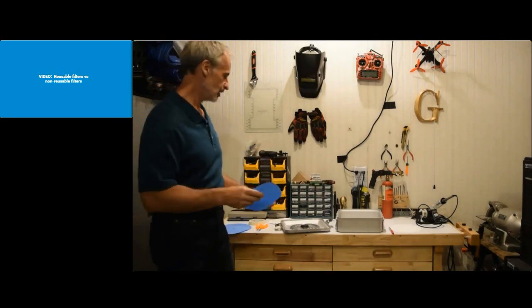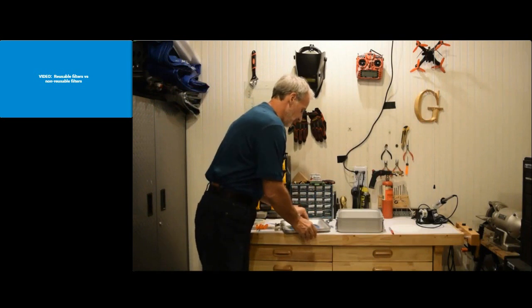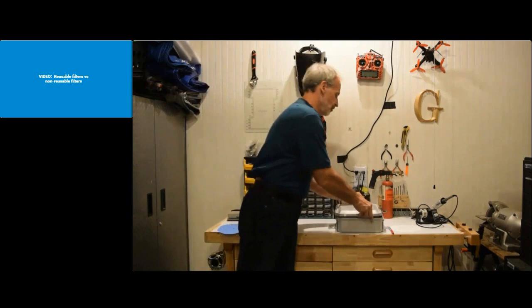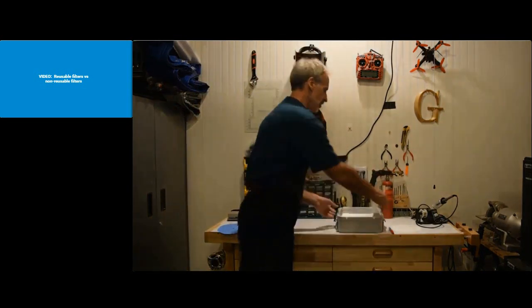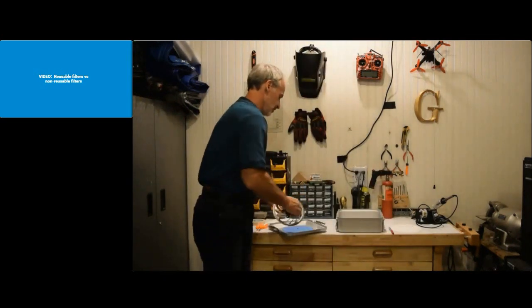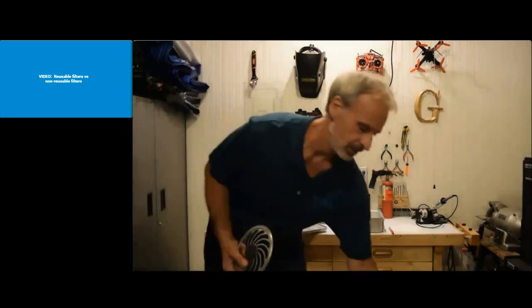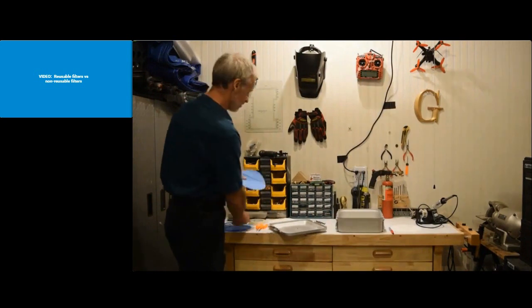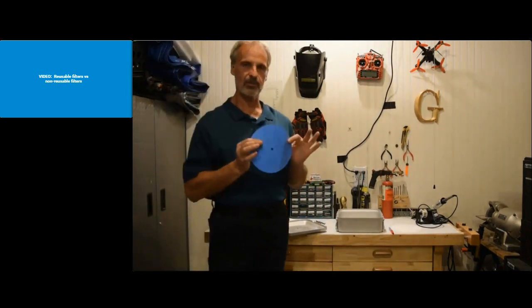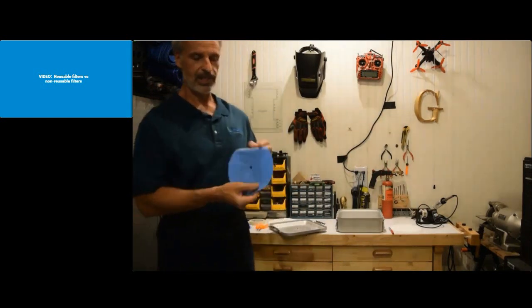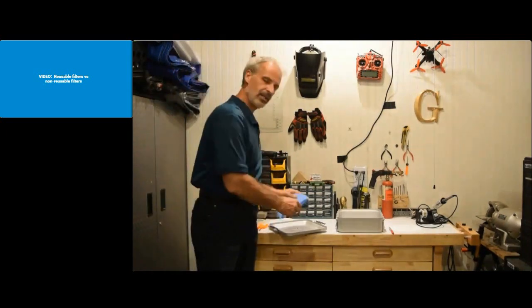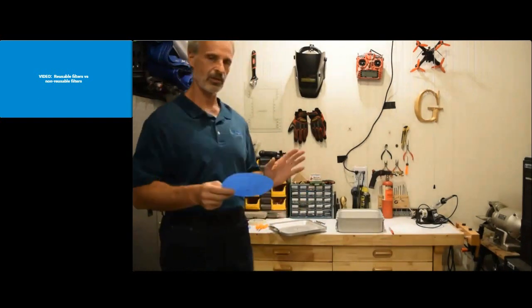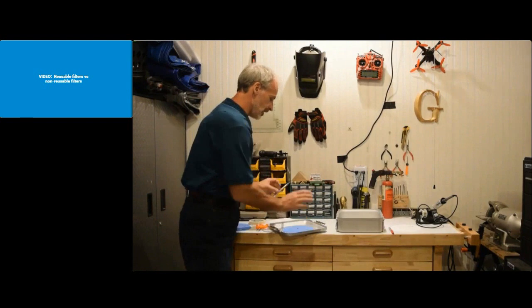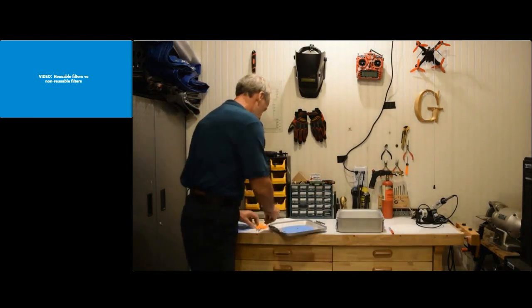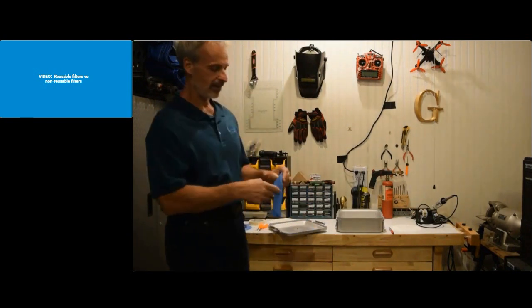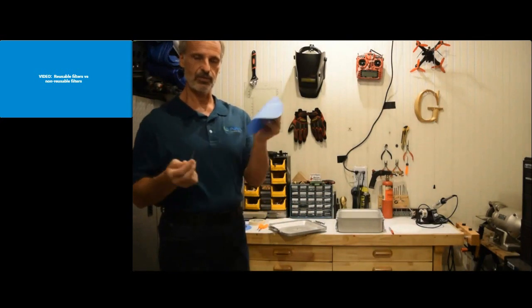So what you do is you would take the lid, put a filter in, the box goes through the autoclave. When it's done, the lid is removed, the holder is removed, and the filter is thrown away. Put a new filter in, repeat the cycle. The problem with disposable filters is they are very thin, very paper-like, and they can wrinkle, they can deform, they can be put in crooked. They take some time to make sure they're seated well, so it's a waste of resources there as well, and they can be problematic. Another thing which can easily happen, as I showed before with the blue wrap, is that these things can be poked very easily. As you can see, sharp equipment can go through the product very easily.